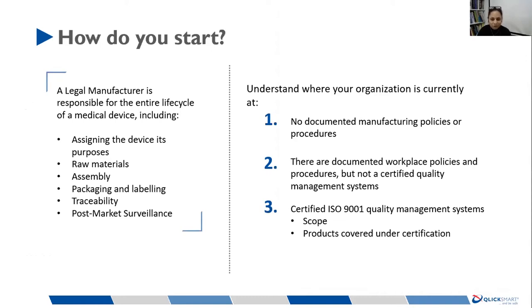So, how does one start? As Fiona mentioned in her presentation, as a first step, it is important to clearly understand what are the responsibilities of a legal manufacturer. A legal manufacturer is responsible for the entire life cycle of a medical device, including aspects like identifying the intended use of the device, all the way to packaging and labeling. And once the device is in the market, monitoring how the device performs as part of the post-market surveillance responsibilities.